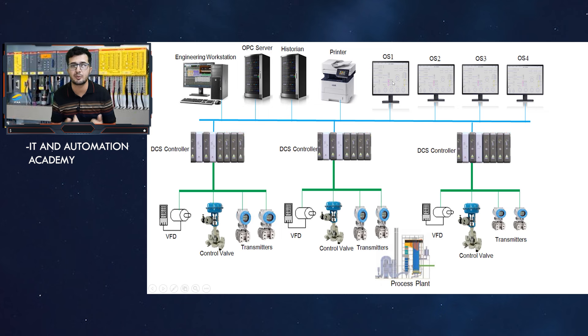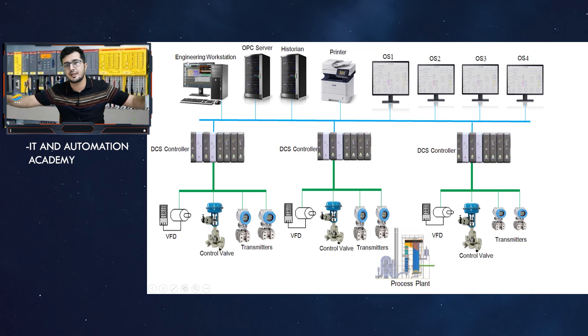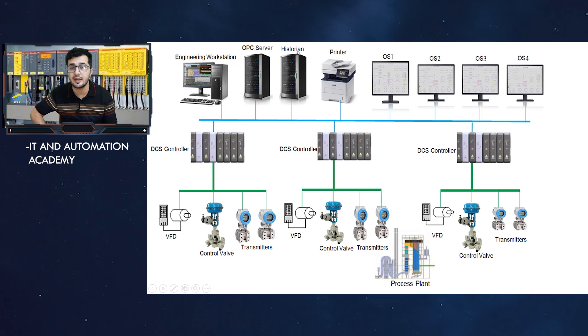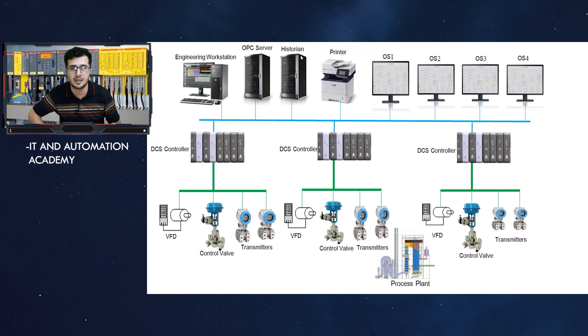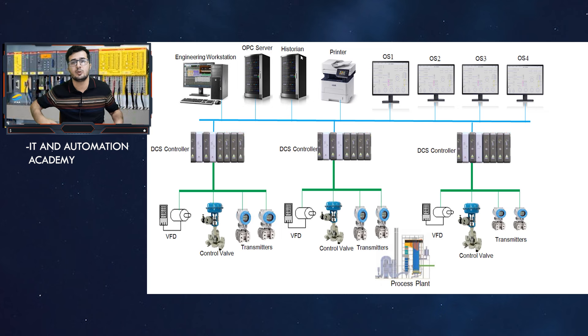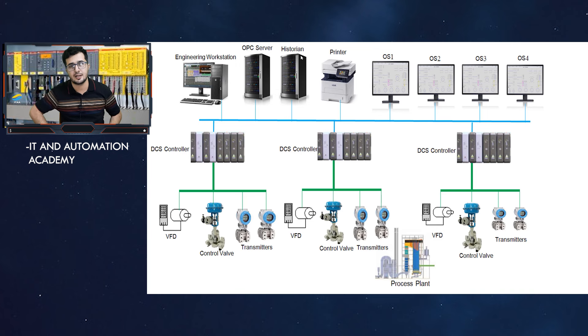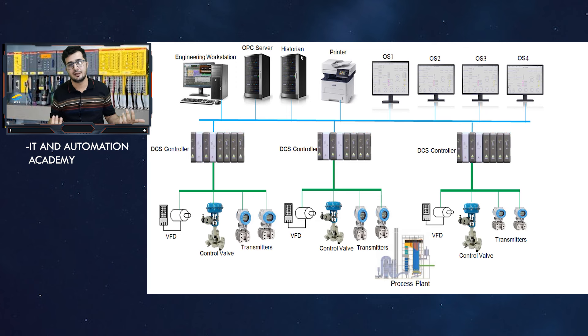The engineering workstation is different from the operator screens — I will talk about that in detail in coming sessions. The engineering workstation is where you create the graphics and configure the system. Then there is the historian. Normally, DCS systems have limited onboard storage, so you cannot retrieve historical data. For example, if I want to know what the temperature value was three years ago or even yesterday, without a historian I cannot store or retrieve that data. The historian stores all your historical data so you can go back in time.